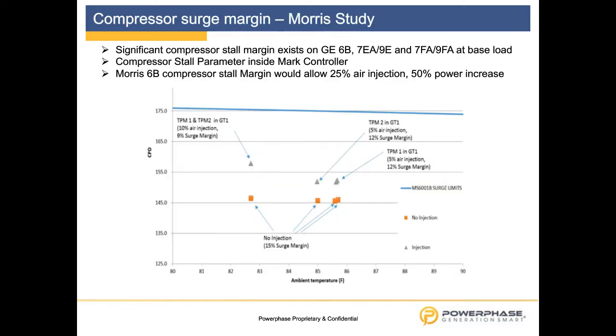In the following, I would like to go into some real-time data on the compressor surge margin. This is on a 6B. On the lower side of the graph, you see three orange squared points, which are the compressor discharge pressure without air injection. It is about 15% off the surge limit, which is the blue line at top, the surge alarm. Then you see two or three triangled gray points on the right upper side. These are the compressor discharge pressure parameters with 1 TPM injection, which is a 5% injection. And in the left upper corner, there's one particular point in which we have injected 10% into the 6B, and you see we are still about 9 to 10% off the surge limit.